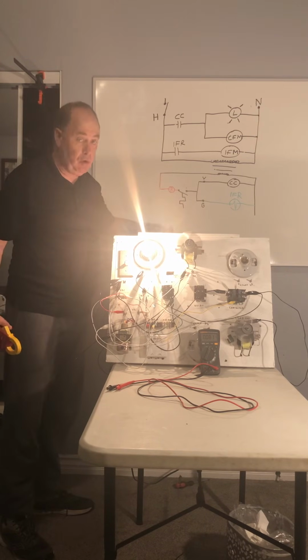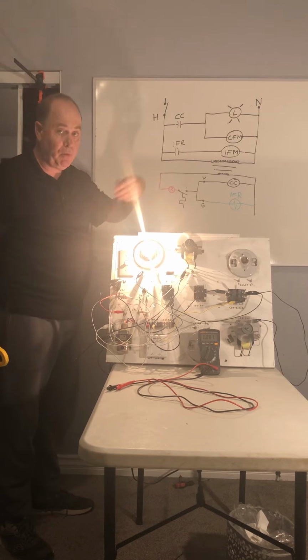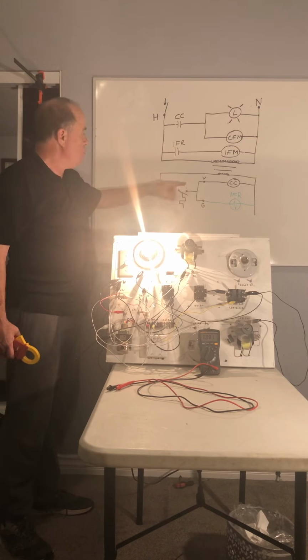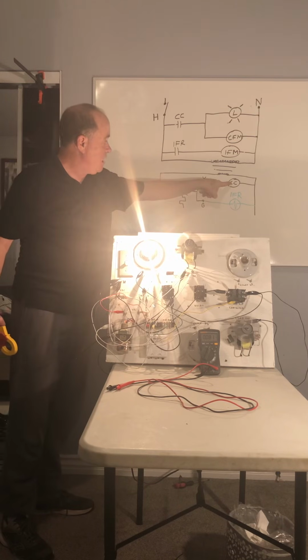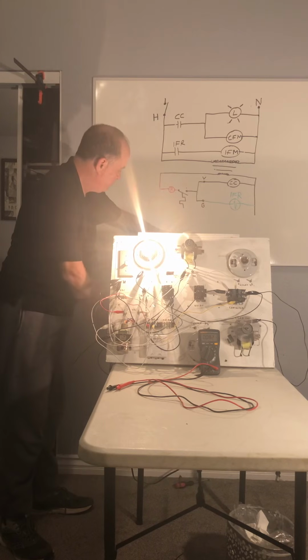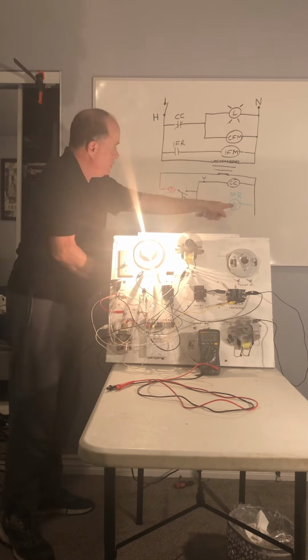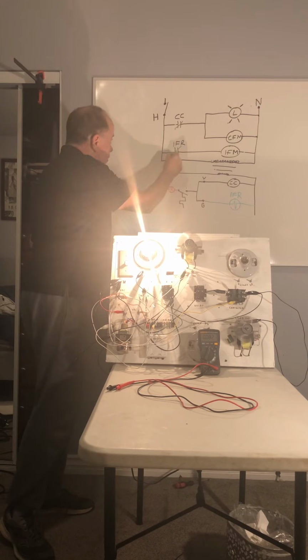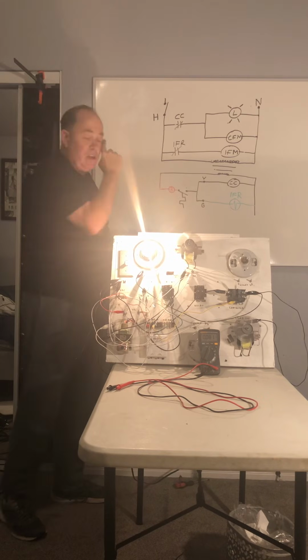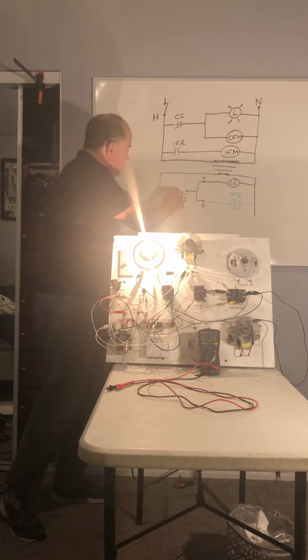And here, when we energized it, or we said we want it cooler in here, and we set the set point lower, saying let's make it 60 in here or whatever, we closed this contact and we energized the contactor coil, and this closed here. And also, when this energized, the indoor fan relay, this closed, and our electrical loads came on. Again, the first thing we did once we turned the power on was to close our thermostat by saying, hey, we want it colder in here.